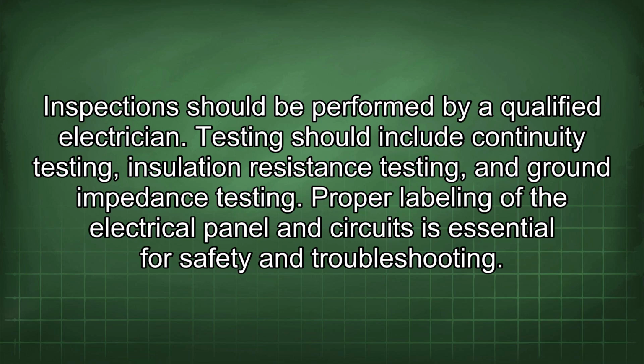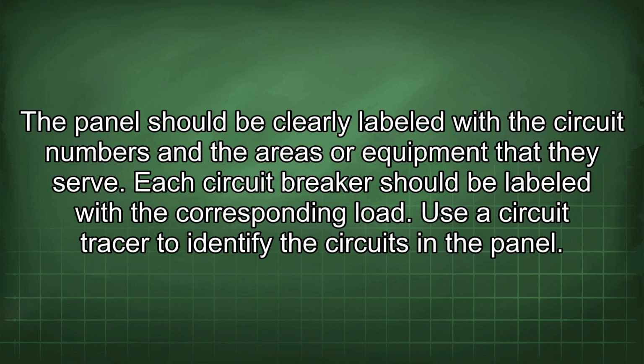Proper labeling of the electrical panel and circuits is essential for safety and troubleshooting. The panel should be clearly labeled with the circuit numbers and the areas or equipment that they serve. Each circuit breaker should be labeled with the corresponding load. Use a circuit tracer to identify the circuits in the panel.